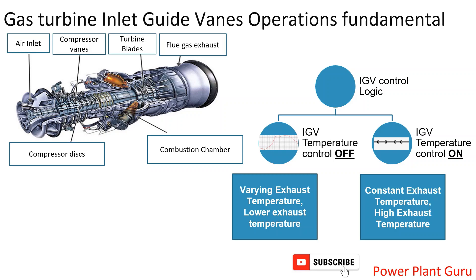The maximum exhaust temperature maintained is around 580–590°C for a Frame 9 gas turbine, and 560–570°C for a Frame 6 turbine. Higher temperature means higher steam generation in the HRSG, higher steam generation means higher power generation in the steam turbine generator in a combined cycle plant. So IGV temperature control mode ON increases the overall efficiency and power output. Before switching to this mode, you should check the history of IGV operation and past maintenance records.